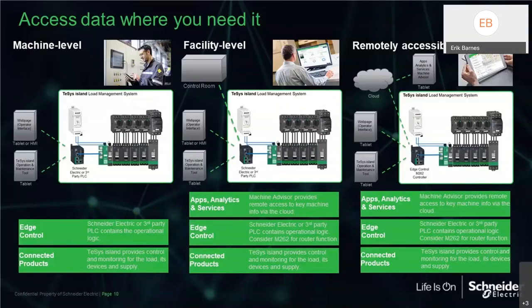So let's talk about the different methodologies here, right? Now that we can see more things with TeSys Island on the devices, on the power supply coming in, on the loads and their performance, and monitor for certain issues, we can now do things with that data, right? We can stay at the machine level. Obviously, you could send that information to a PLC, which can then communicate via HMI, or maybe pilot lights, however you want to do it, to alert the operator or the maintenance technician that some attention or some action is needed, right?